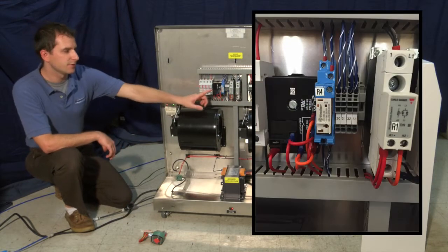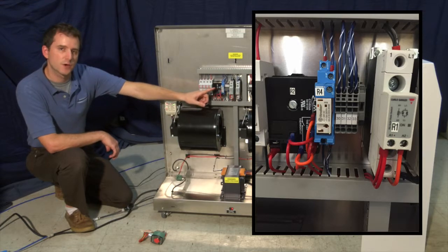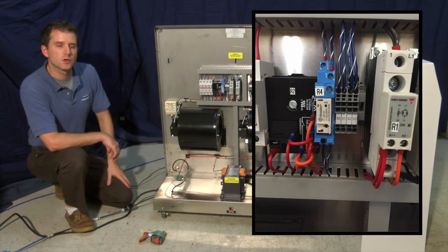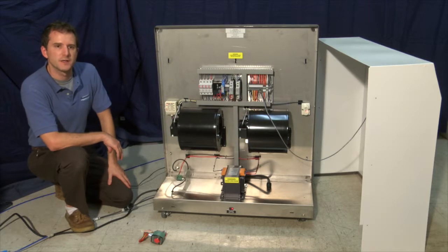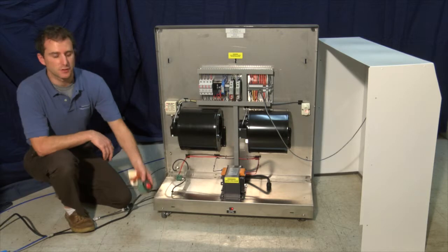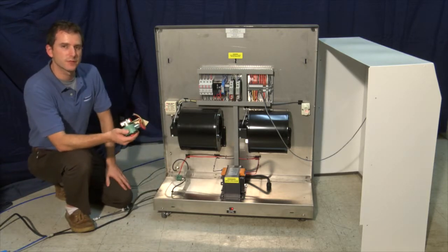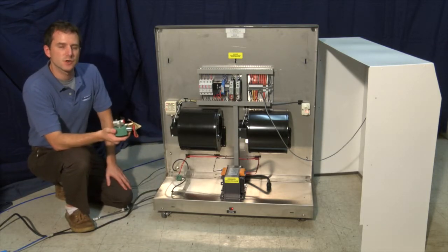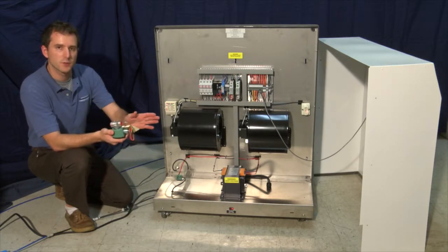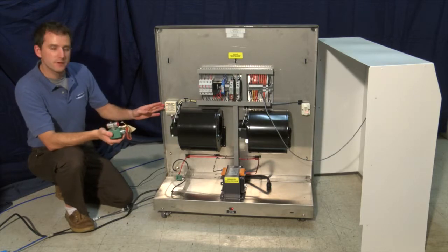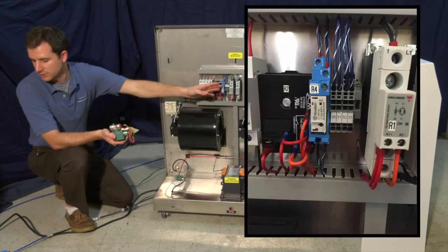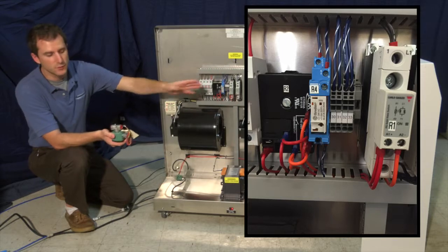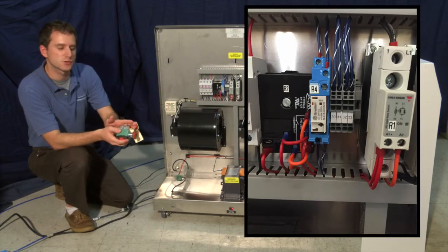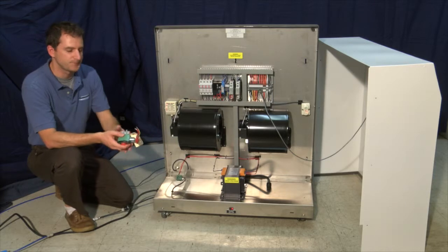There is also a set of notification contacts marked 30 and 31. These will close and can be remote monitored by another system for leak notification. There is also an optional secondary solenoid known as the flood guard solenoid. This would be installed in the incoming water line and is a normally open solenoid allowing water to pass through. When the water guard is triggered, it would power terminals 32, 33, which would power the solenoid and close the water supply completely to the unit.